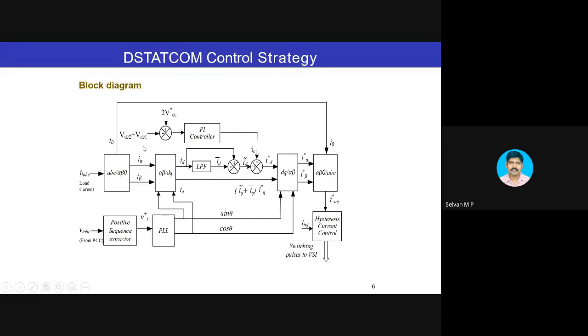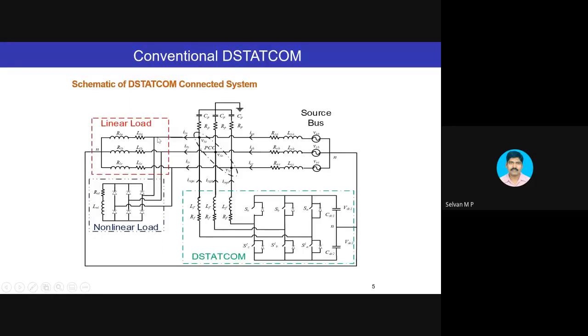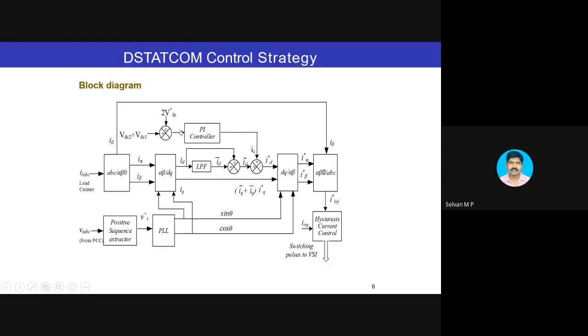I will have that DC voltage I have to maintain, because this DC is a capacitor. Capacitor voltage I have to maintain. To maintain capacitor voltage, I can draw a little bit of real power from the system to charge the capacitor. So that is included in this loop. And if you see here, ID component, I am passing through a low pass filter to find out what is the constant DC quantity. The remaining one is the oscillating component, which indicates the presence of harmonics.